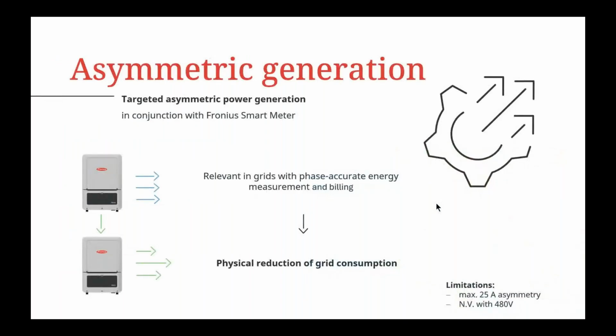Also, we have brought in our software designs for asymmetric generation. What does it mean? What you usually see is that inverters produce power equally on all phases, and at the time of excessive power that you are not using, it is fed back to the grid. But with this asymmetric generation design and the software that we have integrated in our inverters, not only for Verto but also for Tauro, Gen 24s and the Snap inverter that you are already using in the market, you can upgrade the software and generate uneven, asymmetric power on each phase. So if on one phase you want to feed less power and on the other phase you want to feed more power, you can do it asymmetrically.